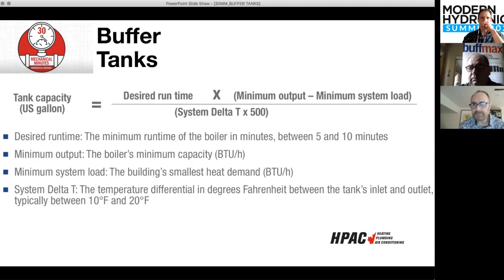Now, I wonder if people do get confused. I know I did. The difference between a buffer tank and an indirect tank. Maybe, Nico, you can start and Steve jump in. Yeah, so they are two different pieces of equipment. An indirect basically produces domestic hot water by indirectly getting boiler water from it, and it makes domestic water, but it really does nothing. The typical indirect does nothing to be like a buffer for the boiler.